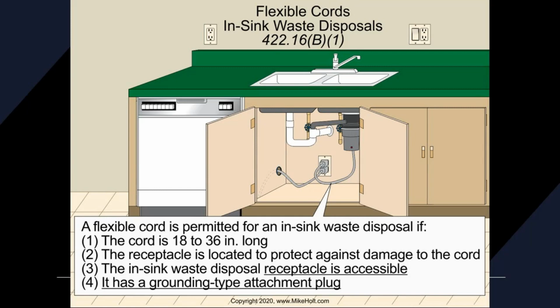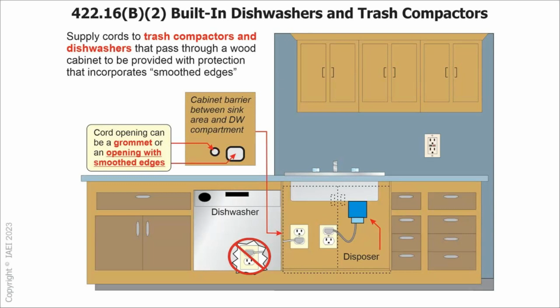So, in Article 422 under appliances, there is a requirement that your disposal cannot have a cord shorter than 18 or longer than 36 inches long. Dishwasher is going to be 6 feet, right? So these are great questions that they always dig up for your journeyman's test. In addition to this, this disposal receptacle has to be accessible. It has to be a grounding type attachment plug. Can't be a 2-wire. And it has to be GFI'd in the real world too.